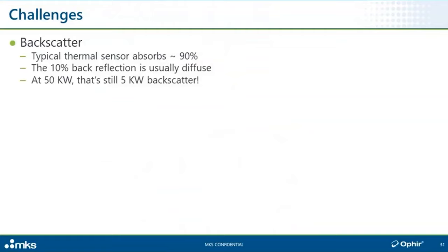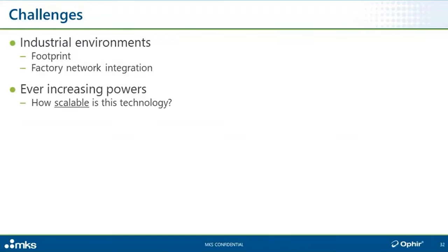Another challenge is backscatter. Typical thermal sensor absorbers absorb something like 90%, a little more, a little less, depending on the wavelength. The other 10% is not being absorbed, meaning it's being reflected. Typically these absorber materials are matte, so the reflection is diffused, but still, if we're talking about many tens of kilowatts, then that's many kilowatts that are being backscattered back out into the room, and that could definitely present a safety hazard to personnel that are in the area.